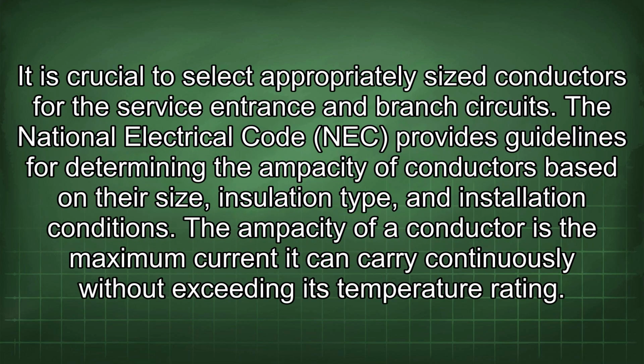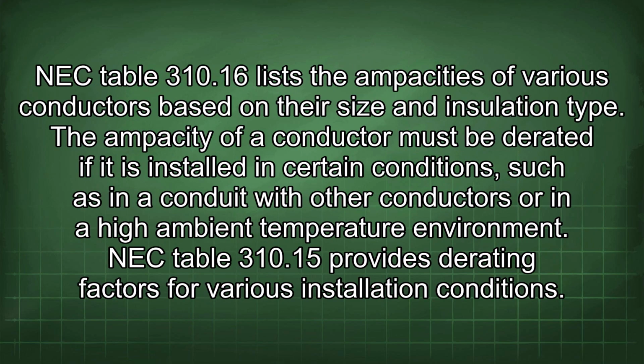It is crucial to select appropriately sized conductors for the service entrance and branch circuits. The National Electrical Code (NEC) provides guidelines for determining the ampacity of conductors based on their size, insulation type, and installation conditions. The ampacity of a conductor is the maximum current it can carry continuously without exceeding its temperature rating. NEC Table 310.16 lists the ampacities of various conductors based on their size and insulation type.